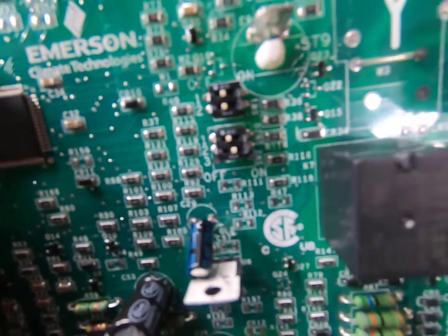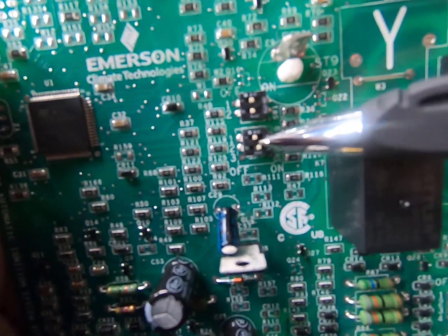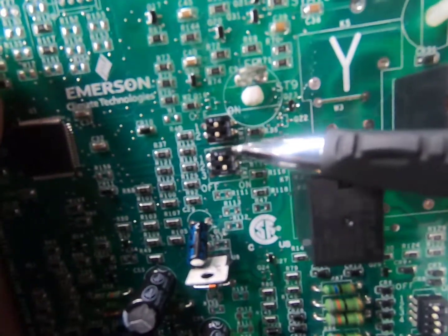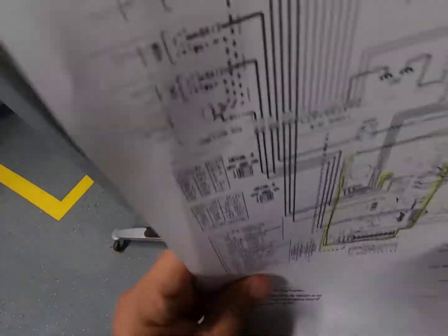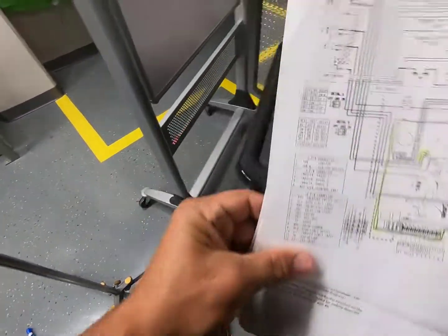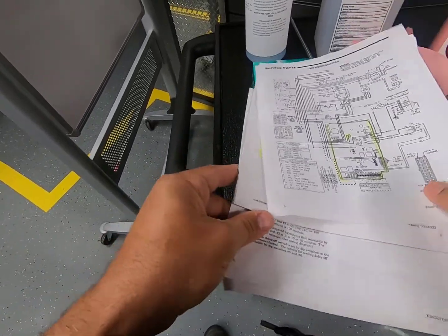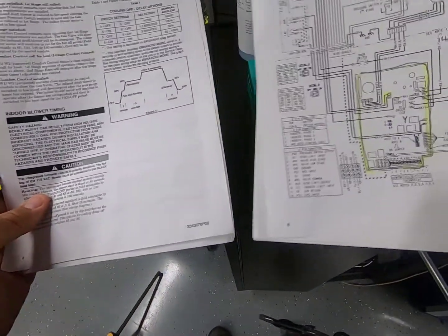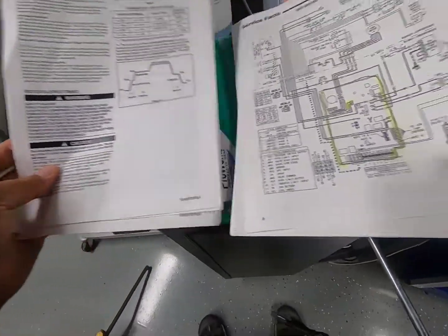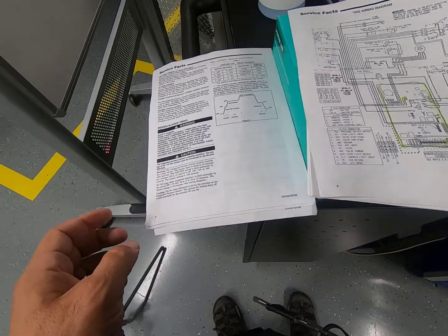Isn't that cool? And all that this one block, these 2 switches, is doing is adjusting the amount of time the blower runs after the furnace finishes its heating sequence. After the heating thermostat is satisfied and the furnace goes through its shutdown sequence, how long is that blower going to run? It's controlled by these 2 dip switches, and I know that because I know how to read my service facts. You would be amazed at how many people work out in the field for years and years and never figure this stuff out. That's why we're doing it here.